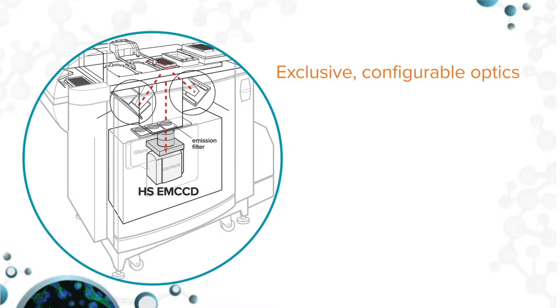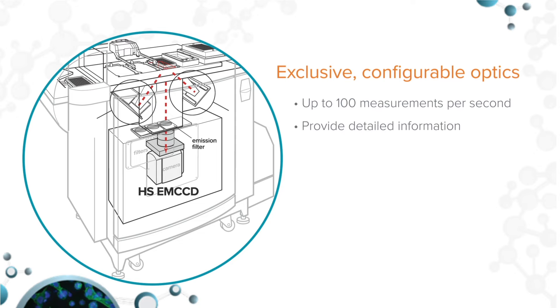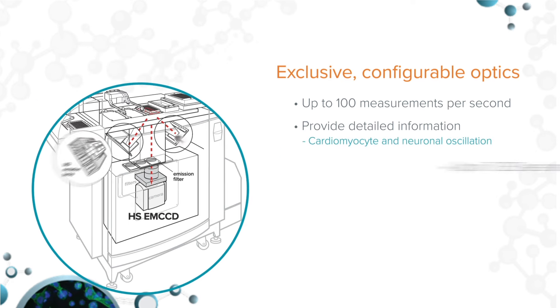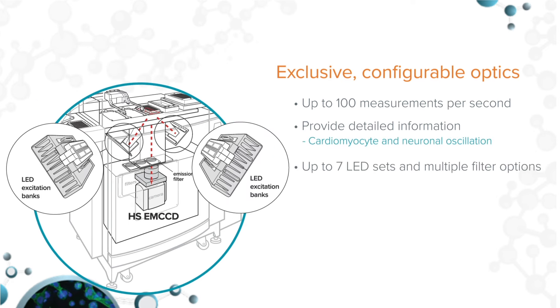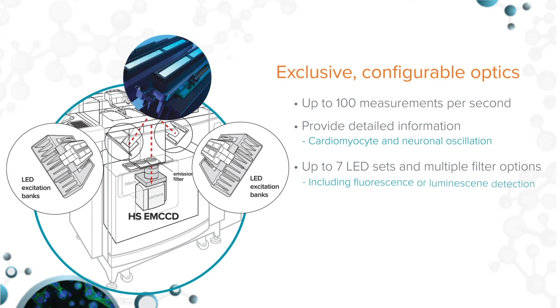A newly enhanced HS-EMCCD camera option allows for up to 100 measurements per second and provides detailed information about cardiomyocyte and/or neuronal oscillation. Up to 7 LED sets and multiple filter options, including fluorescence or luminescence detection, are available.